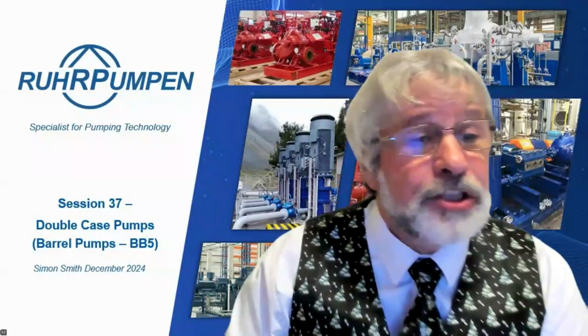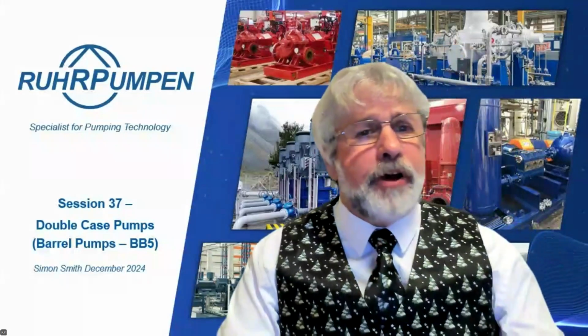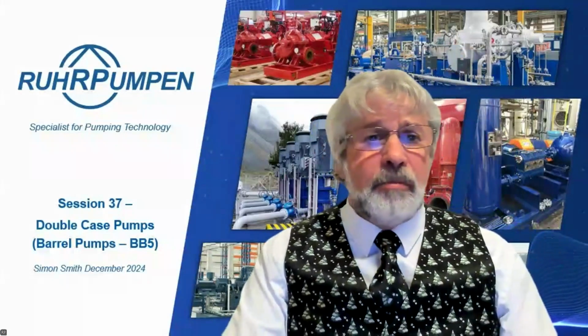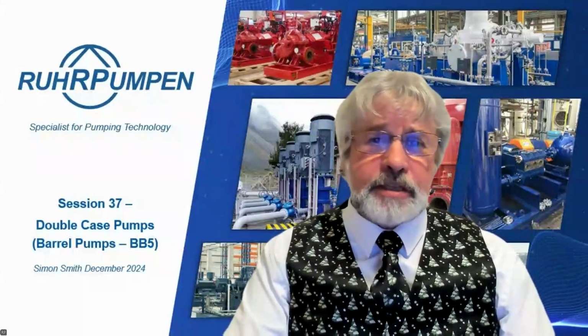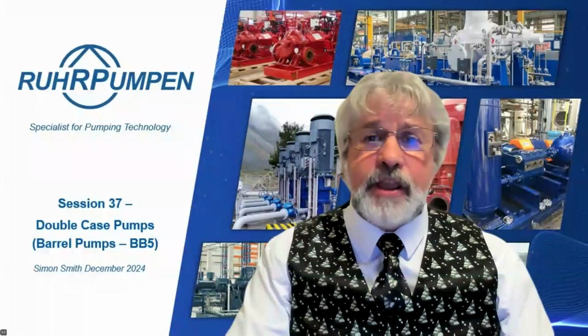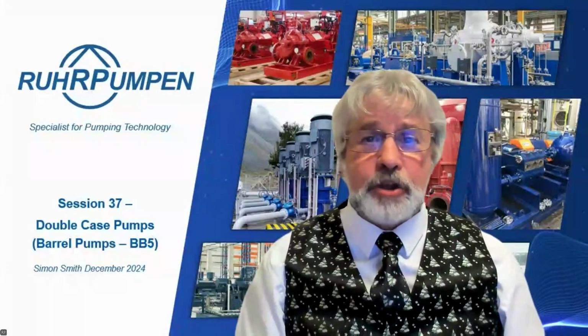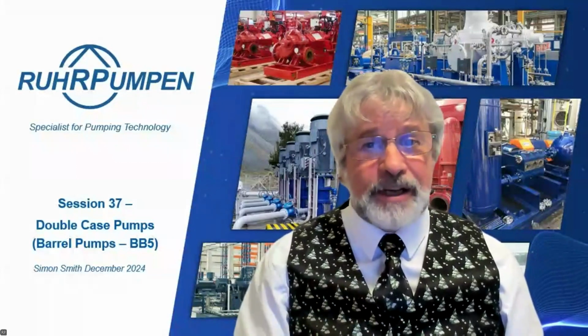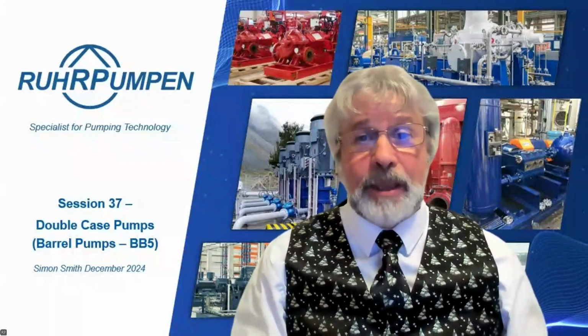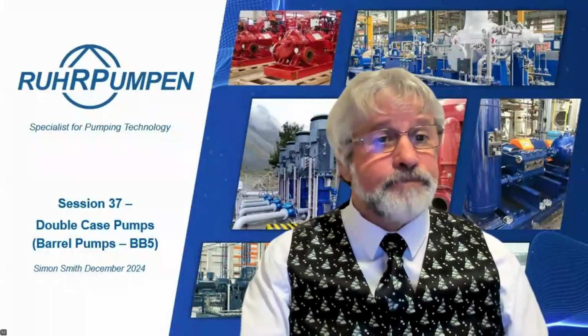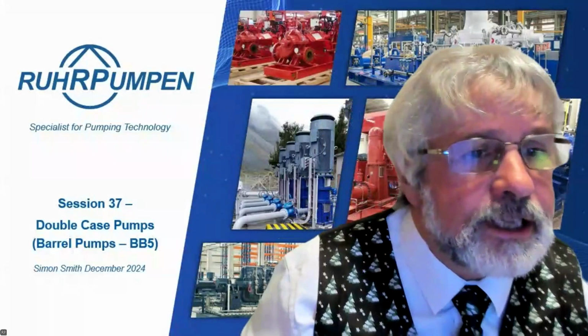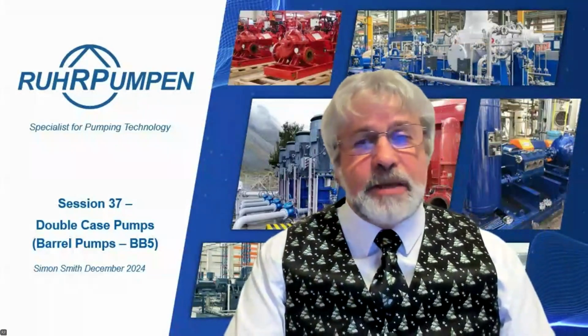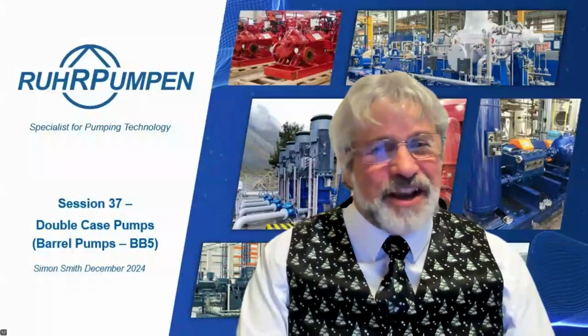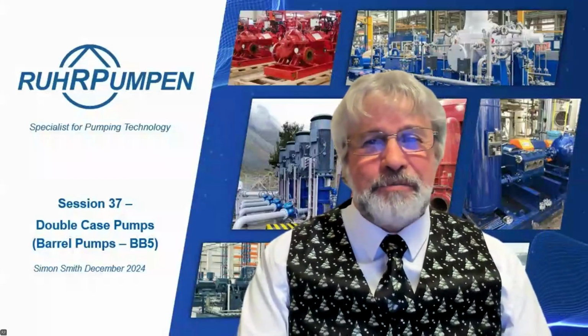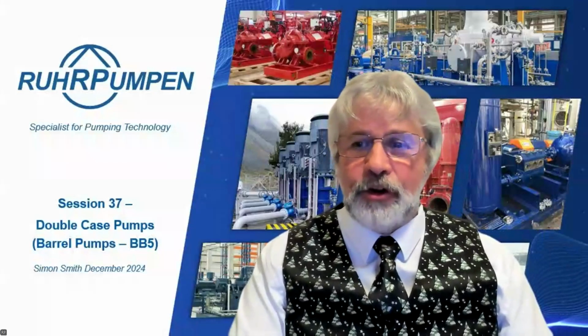Damesh Kuna Panchal says, maximum speed limit of BB5 pumps for 10 stage. Practically no limit. I mean, we can do them at 6,000 RPM as necessary. These are engineered special pumps, remember. So we're doing a torsional and critical speed analysis on every pump. It will be designed for that service. Zinedine says, for which power do we need a hydraulic tilting pad? No easy answer. The application engineer will work it out on each case.